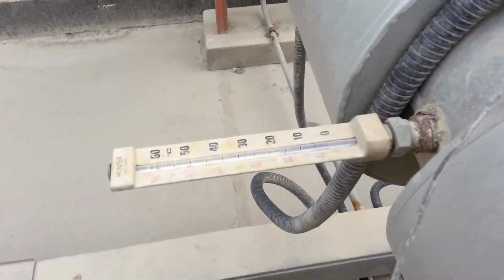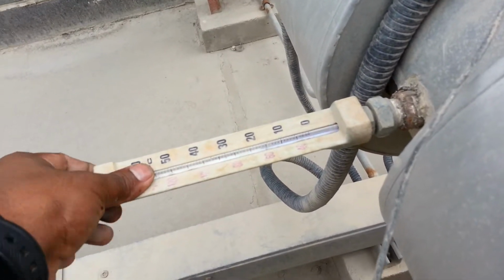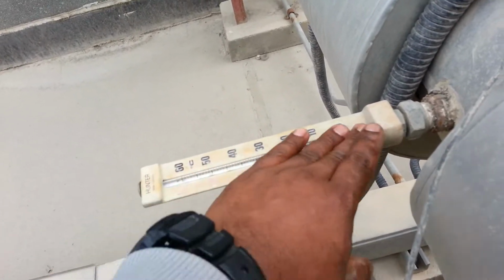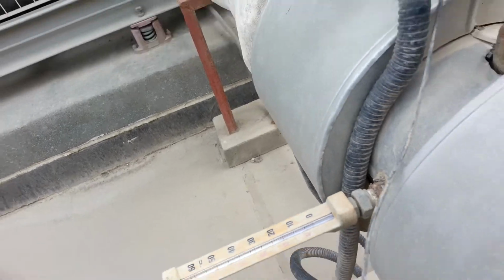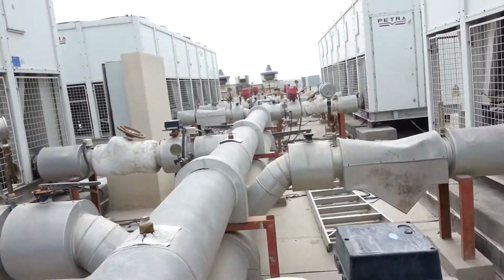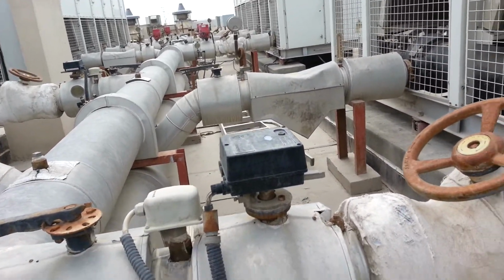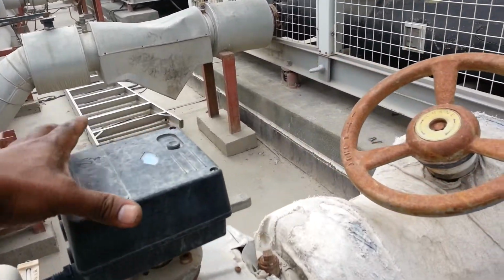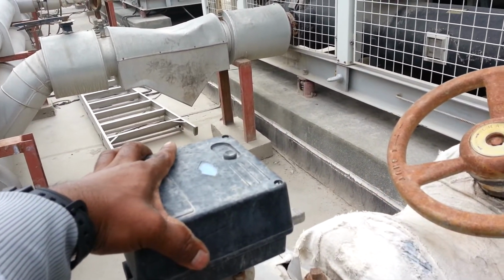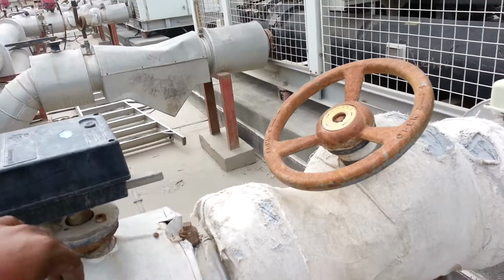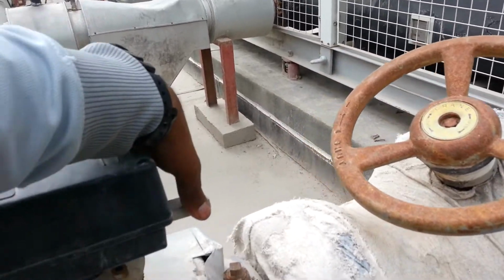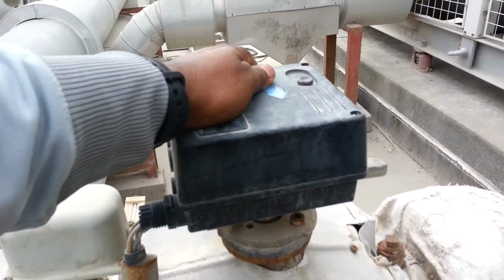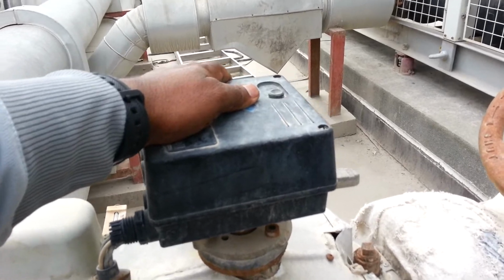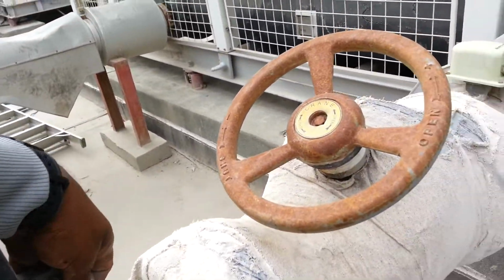Here you can see a scale gauge. This one shows the water temperature. We can see the water temperature manually. This is also a motorized butterfly valve, and here there is a manual switch. If this is working through the DDC, if there is any failure in the DDC, then we can manually operate this valve.